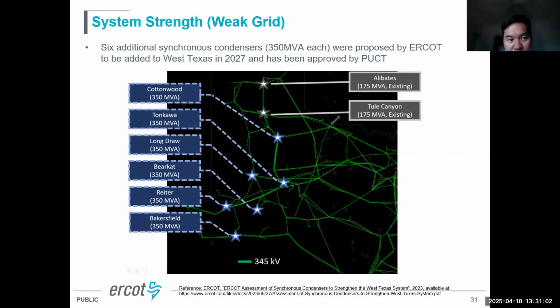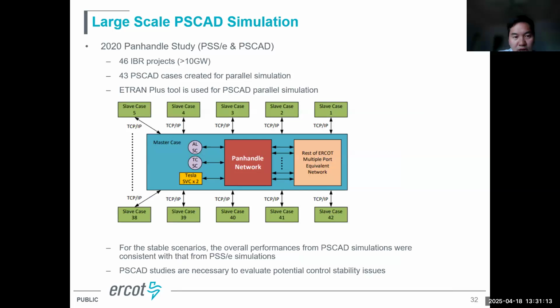Last year, we proposed 6 additional synchronous condensers, each 350 MVA, for West Texas to increase system strength there. We also ran PSCAD parallel simulations to identify any potential control stability risk—some kind of oscillation at sub-synchronous frequency range that may not be captured in phasor domain or PSS/E simulation.